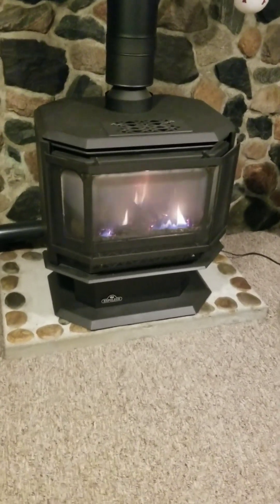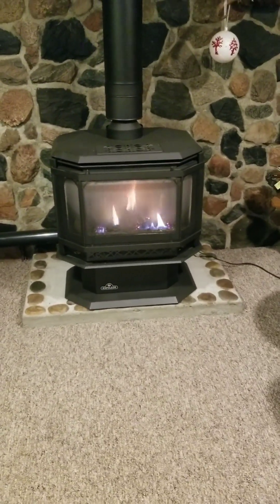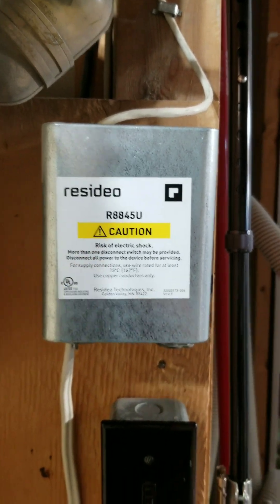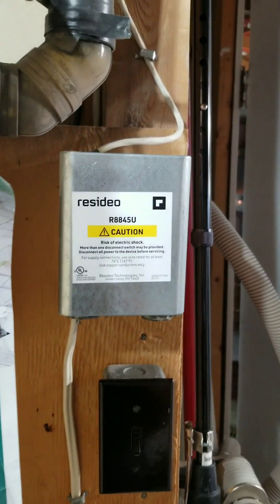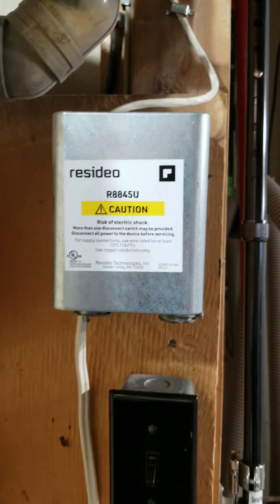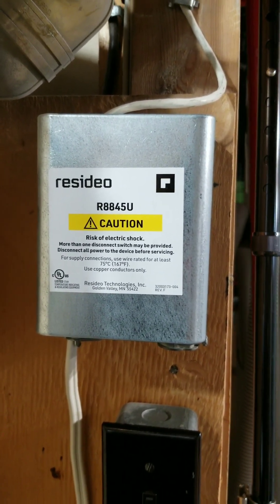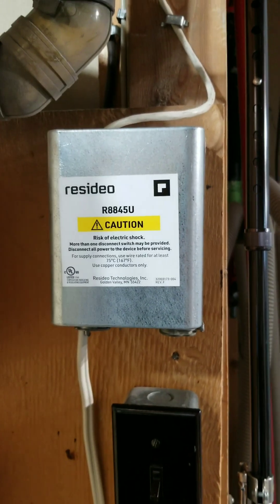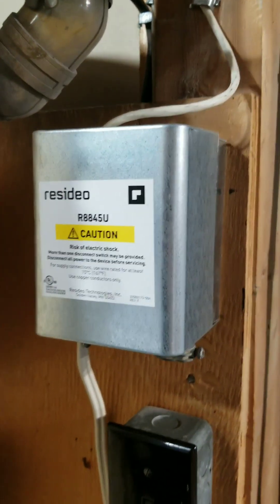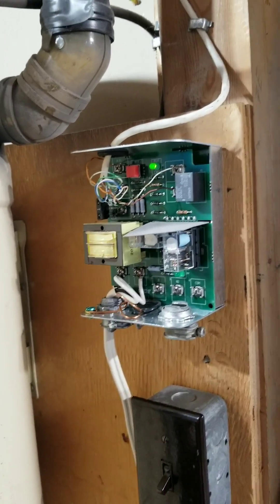That fireplace just has contact closure to either activate it or deactivate it, and was previously operated with a standard thermostat. This is the Resideo R8845U controller — it's a relay controller that takes a control input and converts it to a relay contact closure on the output, which is what I required for the gas fireplace to be activated. I'll pop the cover off and show you.